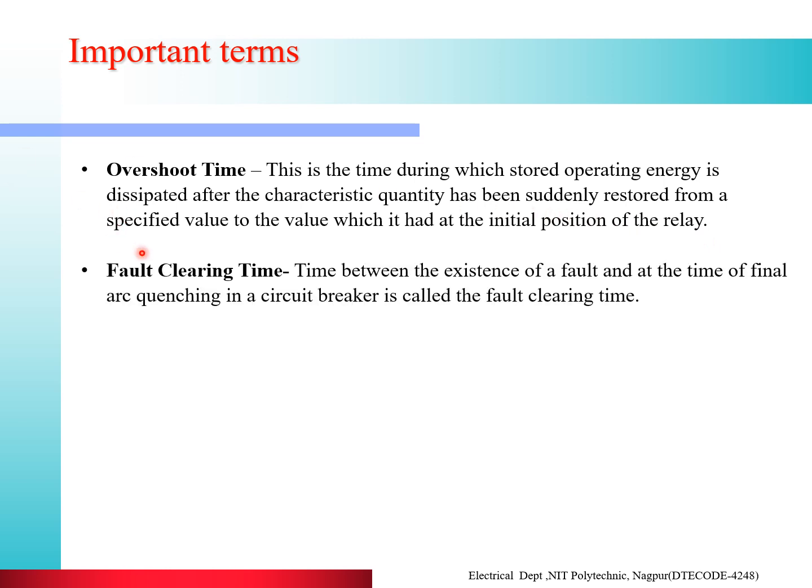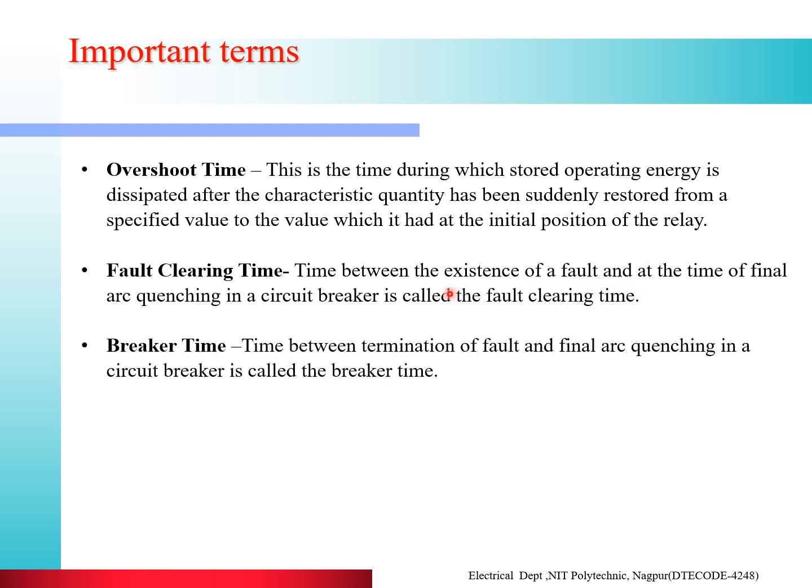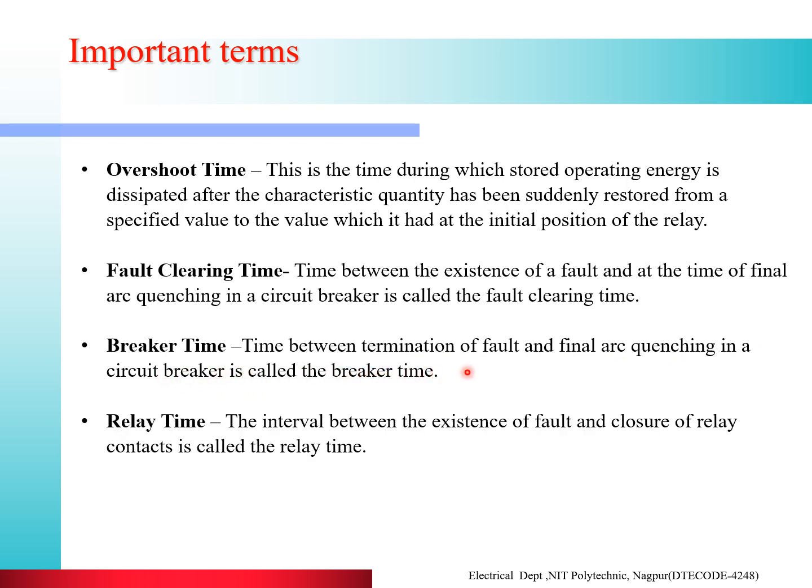Next term is fault clearing time. The time between the existence of a fault and the time of final arc quenching in a circuit breaker is called the fault clearing time. Breaker time: the time between the initiation of the trip circuit and the final arc quenching in a circuit breaker is called the breaker time.